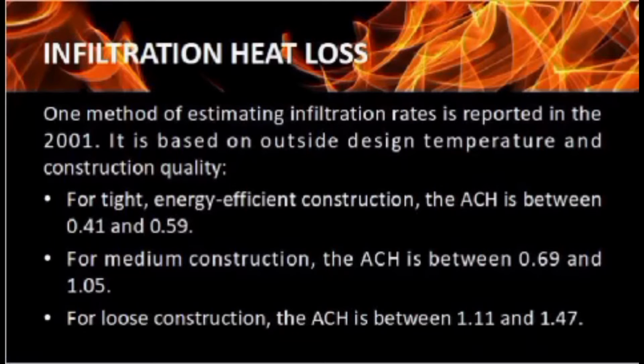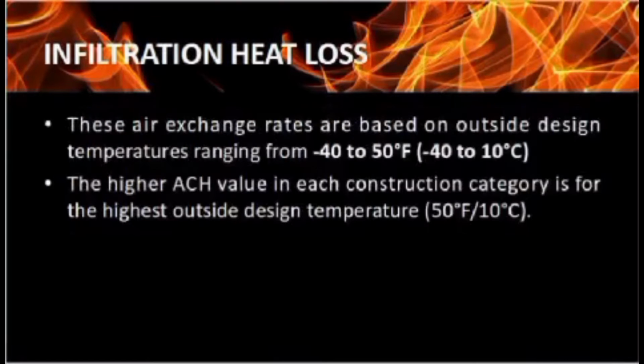One method of estimating infiltration rate. For tight, energy-efficient construction, the ACH is between 0.41 and 0.59. For medium construction, the ACH is between 0.69 and 1.05. For loose construction, the ACH is between 1.11 and 1.47. The air exchange rates are based on the outside design temperature ranging from -40 to 50 degrees Fahrenheit and -40 to 10 degrees Celsius. The higher ACH value in each construction category is for the highest outside design temperature, 50 degrees Fahrenheit and 10 degrees Celsius.